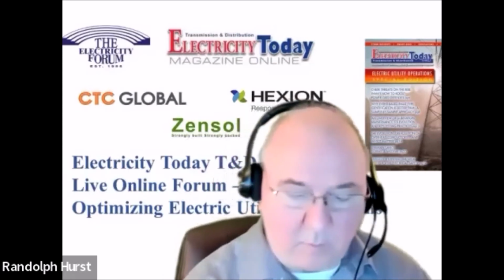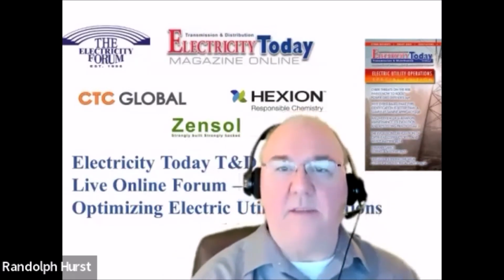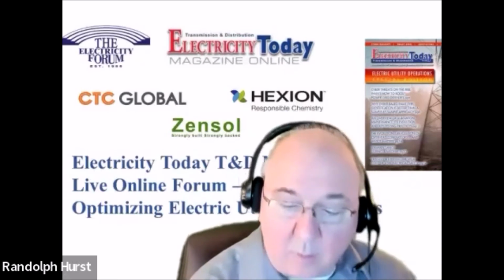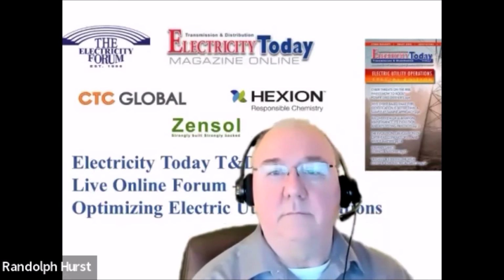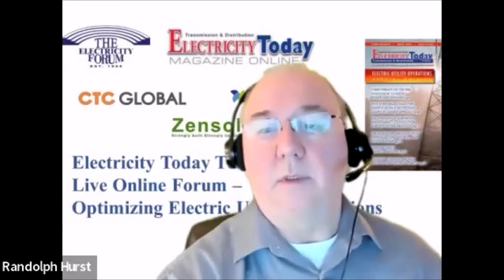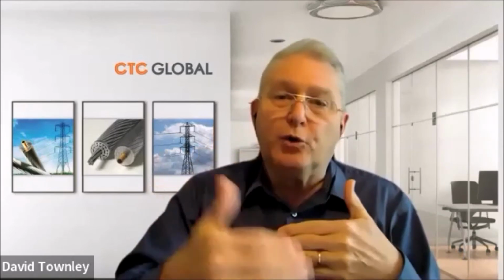Okay, there was another question. How much increased grid capacity does this accommodate? So on reconductoring, that's sort of the same question as for new lines, isn't it? But still looking at reconductoring here, depending on the selection you make and how you as a utility are going to rate that, you'll see 40 to 65% is very common for an operating capacity increase, and we see that very often. So that increase of 50+% is very common.